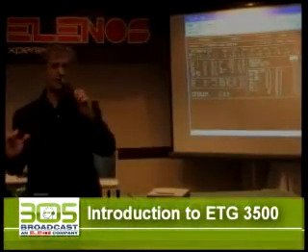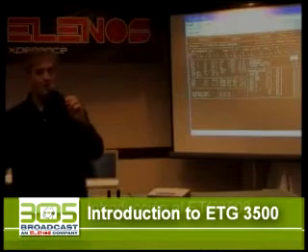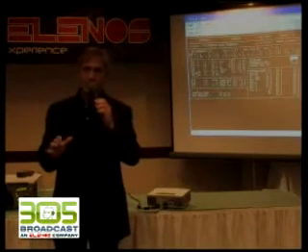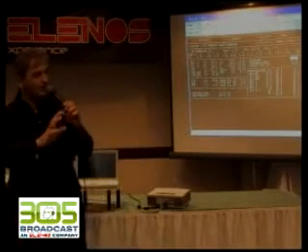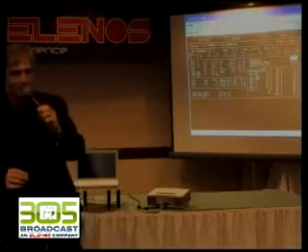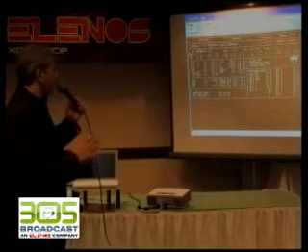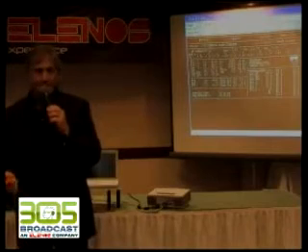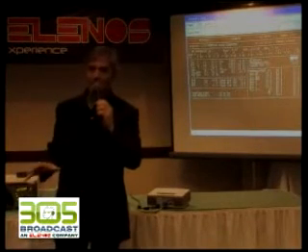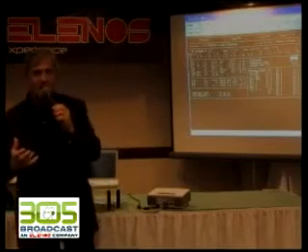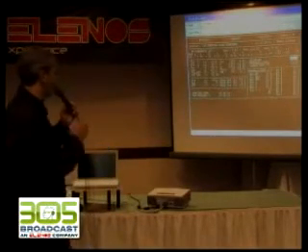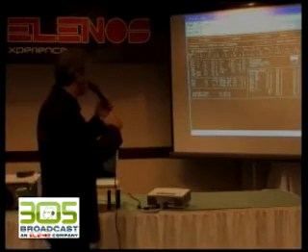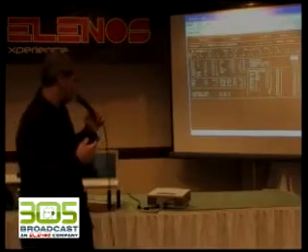The estimated lifetime we have for these power sources is over 10 years. But we cannot guarantee that because we have barely been manufacturing this transmitter for 5 years. However, not one single fan has been damaged so far. That is to say, the projection is true so far. Evidently, it will be able to comply with this if the radio station has good environmental conditions and an effective cooling system, because we can see how the fan increases its speed as the room temperature increases, trying to compensate. Let's cover the transmitter now so you can appreciate how the speed increases and how the equipment behaves.